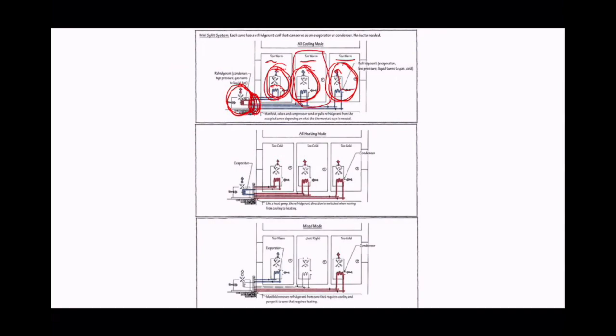But we can do that with a separate, very small ducted system, because you don't need that much fresh air typically. Those type of ducts are actually pretty small, kind of at the scale of maybe a drain pipe. So we can get away with doing that without having to drop our ceiling to accommodate a duct, or figure out how to move a duct around underneath a piece of structure above. Not a big deal when you're just bringing fresh air in, and thermal comfort is being provided by room air. And the other advantage is it's ductless. So this is called a ductless mini split, this particular version that I've drawn.